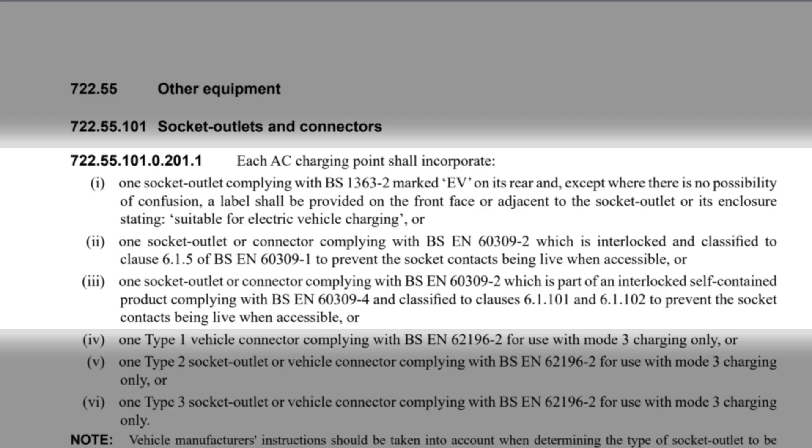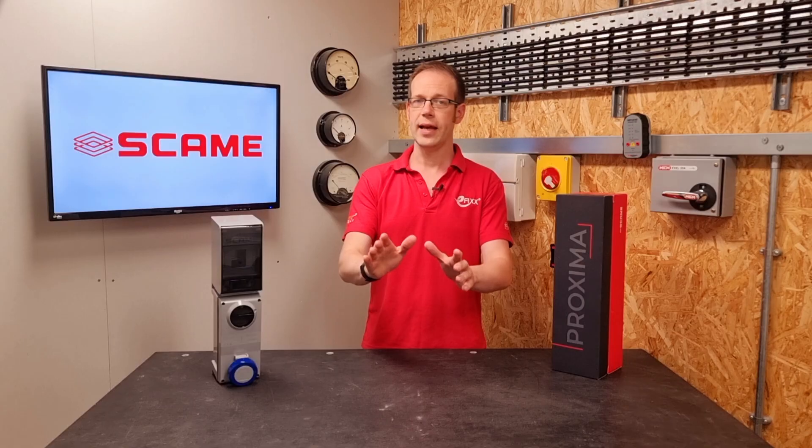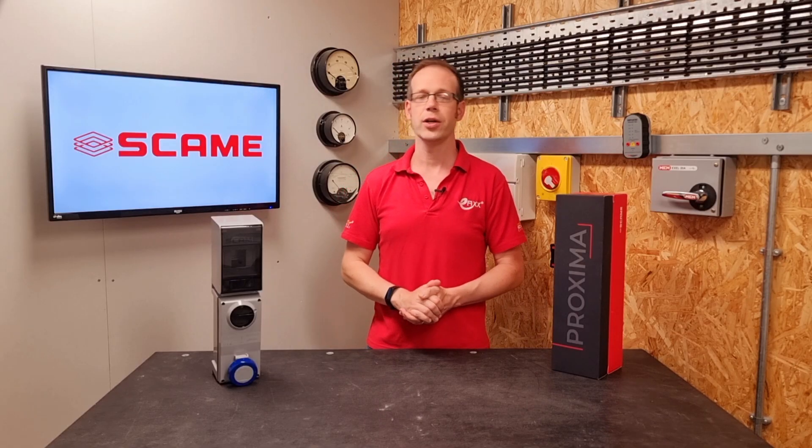or two: one socket outlet or connector complying with BS EN 60309-2, which is interlocked and classified to clause 6.1.5 of BS EN 60309-1, to prevent the socket contact being live when accessible; or three: one socket outlet or connector complying with BS EN 60309-2, which is part of an interlocked, self-contained product complying with BS EN 60309-4, and classified to clauses 6.1.101 and 6.1.102, to prevent the socket contacts being live when accessible. We're going to stop reading there, as the rest of the options relate to dedicated EV charge points.